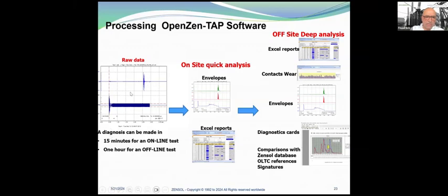So thanks to this, a diagnosis can be made in 15 minutes for an online test, 1 hour for an offline test. So thanks to the software, we calculate the envelopes immediately, and we get what we call an Excel report. This is the on-site analysis, and I will show you in the next slides how we can do analysis and interpretation of these curves.